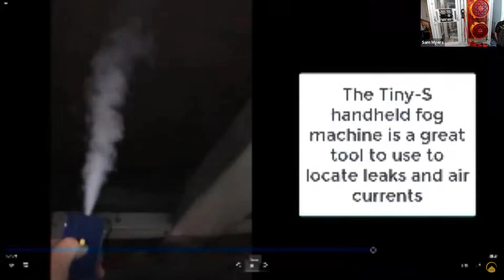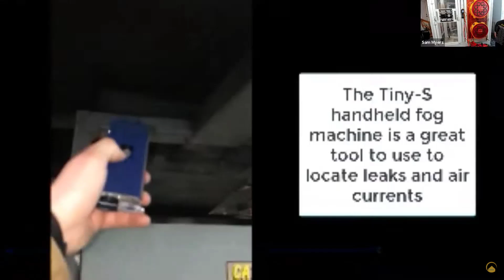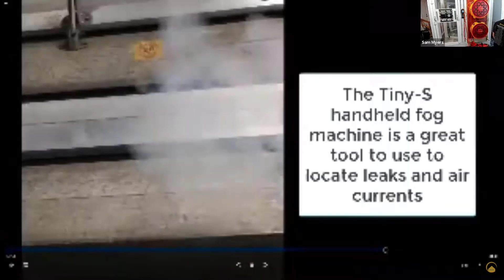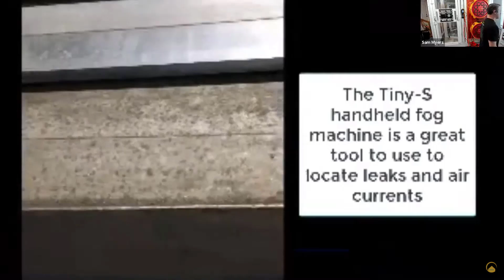So this is that handheld fog machine that I was telling you guys about. And we actually have a new one coming out next month that's half the price and more capable. But I think this was even without the fans running. There was so much stack effect in this building from the leakage that we could just identify it with smoke. And this was those louvers in the elevator canals. And there were really no rubber gaskets on any of those, and they were all seized open. So it was just driving that stack effect even harder than it should have been. And yeah, just having the smoke and walking around to see air currents really helps.